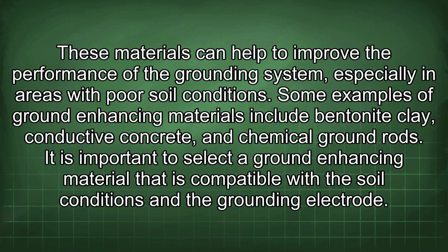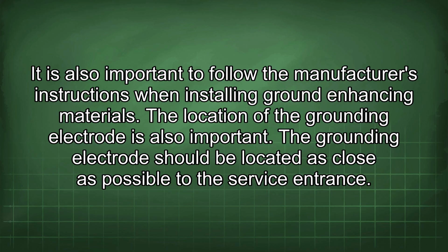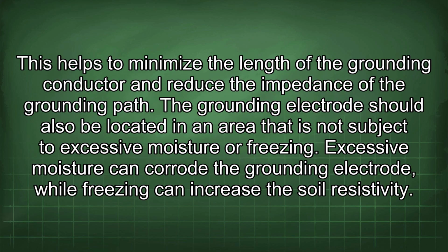It is important to select a ground-enhancing material that is compatible with the soil conditions and the grounding electrode. It is also important to follow the manufacturer's instructions when installing ground-enhancing materials. The location of the grounding electrode is also important. The grounding electrode should be located as close as possible to the service entrance. This helps to minimize the length of the grounding conductor and reduce the impedance of the grounding path.